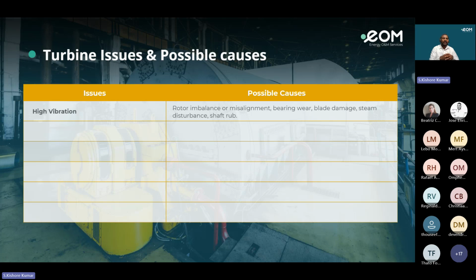If we are not maintaining the proper differential temperature in the turbine, the rotor expands faster and the casing is not expanded in time. So the rotor will come into contact with the stator. Sometimes the fins may rub. The entire rotor will not rub, but the fins on the rotor will rub, and sometimes it forms deep grooves on the wheels, or wears out all the rotor fins, and it will cause heavy vibration.